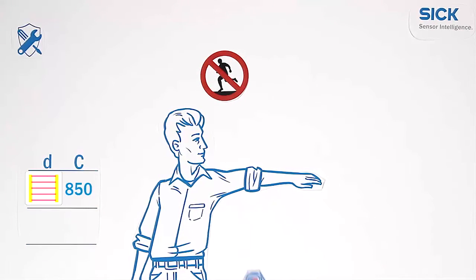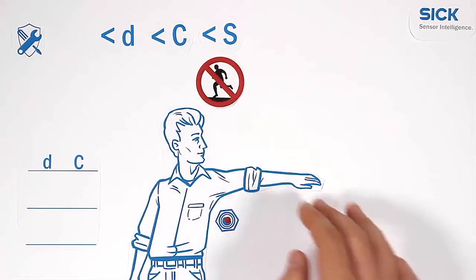A single beam system in combination with further measurements requires 1200 mm intrusion distance. Summarized, the better the resolution, the smaller is c and the shorter is the minimum distance.